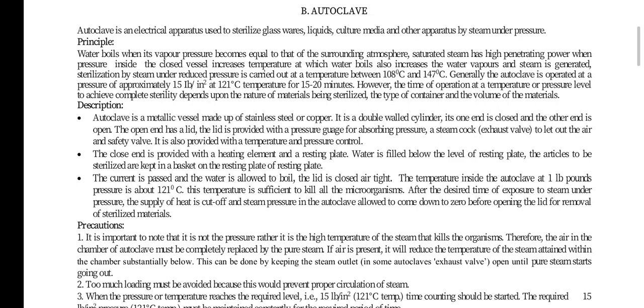Water boils when its vapor pressure becomes equal to that of the surrounding atmosphere. Saturated steam has high penetrating power. When pressure inside the closed vessel increases, the temperature at which water boils also increases, and water vapors and steam are generated. Sterilization by steam under pressure is carried out at a temperature between 108 degrees centigrade and 147 degrees centigrade.